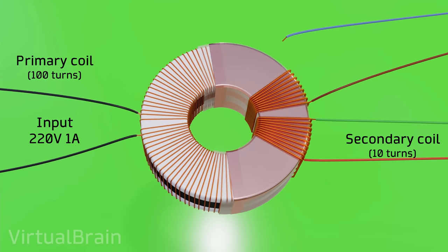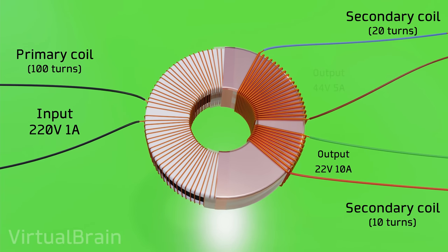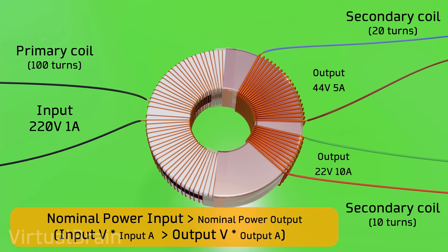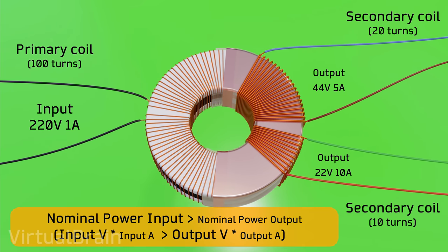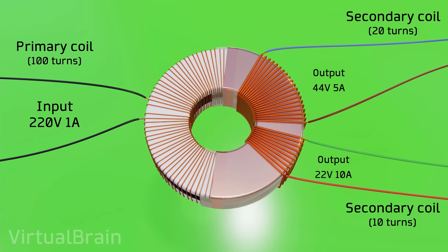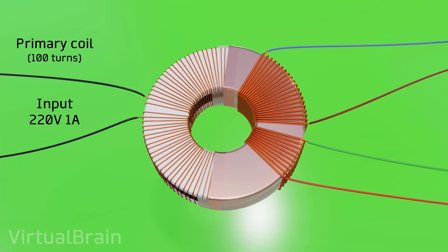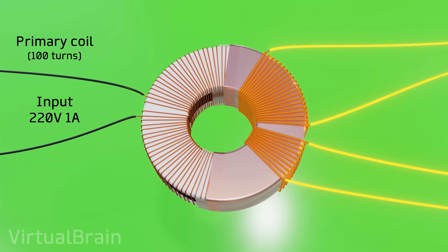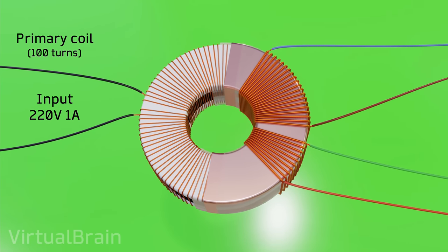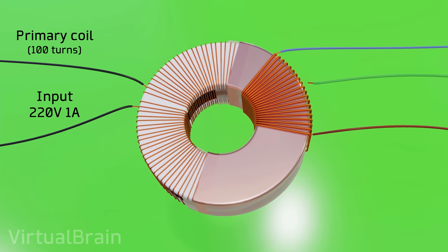Now, if we add a second secondary coil, this time with 20 turns we would have a new output of 44 volts and 5 amps. Although remember that the nominal output power will never be greater than nominal input power. Even though now we would have two possible voltage outputs, this design can be simplified, since we will have 30 turns and 4 output cables. What we can do is merge both secondary coils in one. That is, leave only 20 turns and add an extra cable right on the 10th turn.